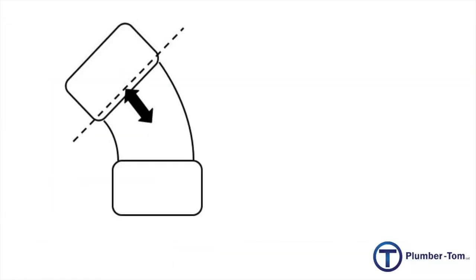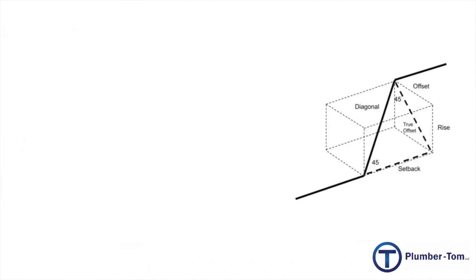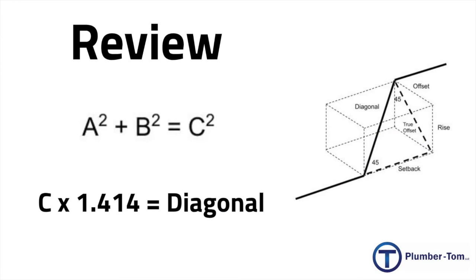Now when you are actually cutting the pipe, make sure to subtract the fitting allowance from the diagonal for each of those 45-degree fittings on either side. To review: when calculating a rolling offset, we first take our offset and our rise — that would be A and B — and put them through the Pythagorean theorem: A² + B² = C². Once we have calculated C, we multiply that by 1.414 to get our diagonal, which is where the pipe actually runs. That is how you calculate a rolling offset.